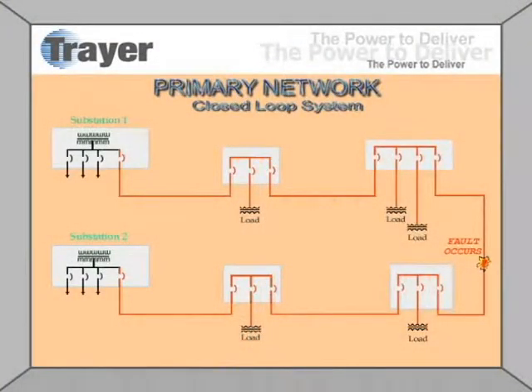When we have a cable fault with a primary network, these are all circuit breakers. And typically you use a circuit breaker for your load, but the source ways are also circuit breakers, not just load break switches. They have fault interrupting capability. So, when we have an event, our relay senses where the fault is and opens the breakers on either side of that bad section of cable. That does two things. It isolates the bad section of cable, but it also interrupts the fault at this section. The substation breakers do not open. It's a local operation for just that line section. And we never lost power to the loads. We never lost the sine wave going to our customers.